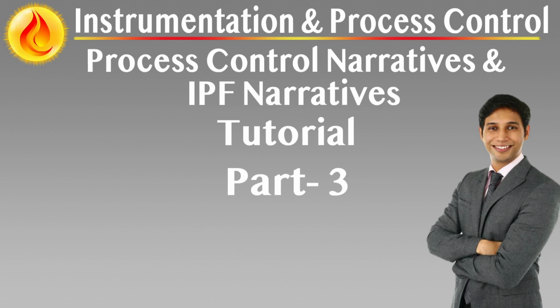Special alarm features. Any special alarm behaviors that support IPF functionality should be documented. This includes re-alarming behavior, e.g. persistent reminder if an IPF remains overridden, alarm inhibition during startup or override, diagnostic alarms for fault conditions in sensors or logic.